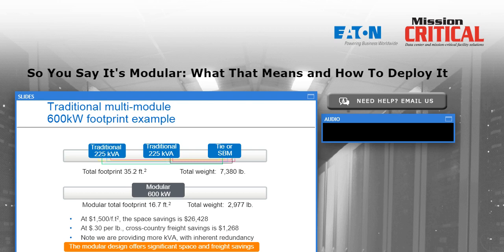So if I do the same thing with a modular UPS at 600 kilowatts, I have 2 300 kilowatt power modules, but they're in the same box, built on the same physical platform. So I have the same building blocks as I have up above. In this case, I have 2 300 kVA power modules, and the tie or SBM cabinet is built into the module itself. They're isolated from each other electrically, but they're actually built together on the same footprint, so I can have one battery backup system that serves that modular 600 kilowatt UPS. So the need for the external tie cabinet goes away. It's built into the machine.